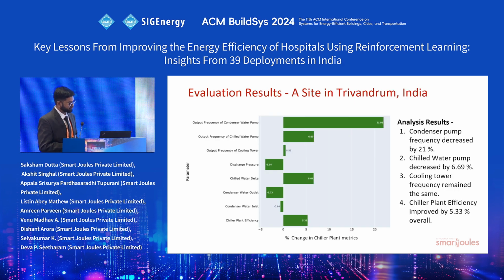So this is, for instance, from a site in India where condenser pump frequency decreased by 21%, chilled water pump decreased by 6.69%, cooling tower frequency remained the same, and the chiller plant efficiency improved by 5.33% overall.